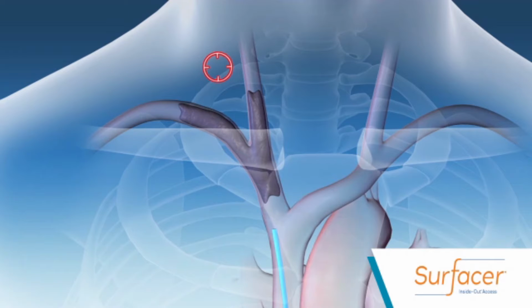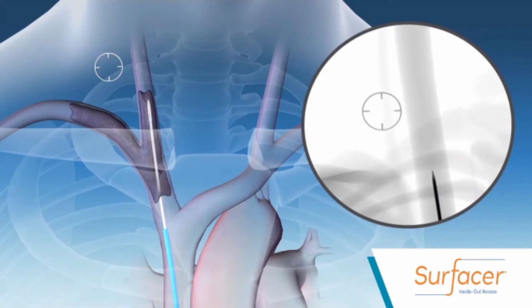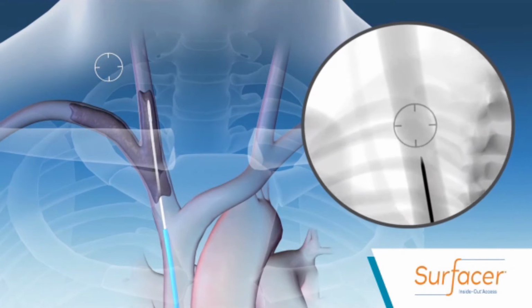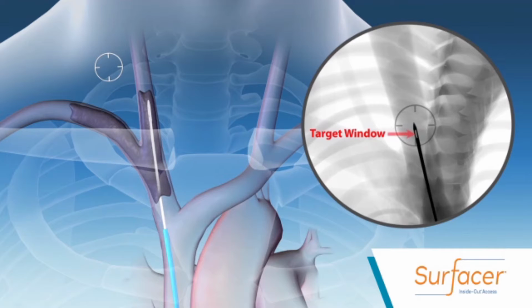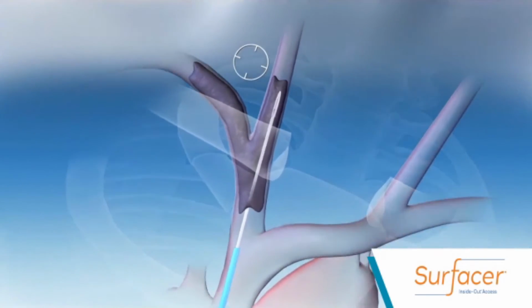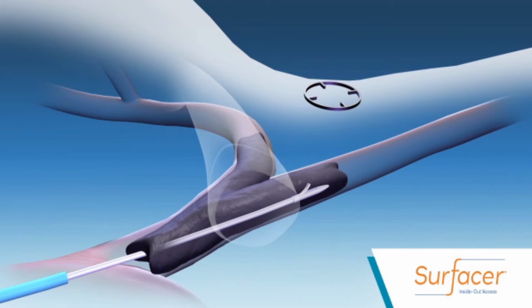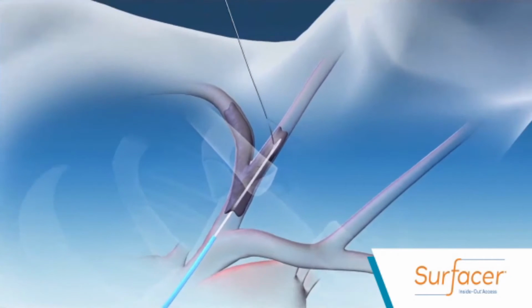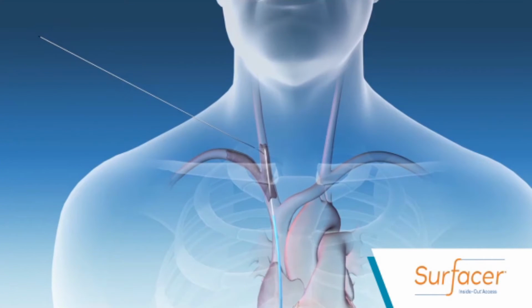After a target is placed on the exit area, the device is advanced into the obstruction. Fluoro is adjusted until the tip of the device is visible within the exit target. The device handle is rotated until the target window appears, and the needle guide is advanced out of the tip. The occlusion acts as a stabilizer as the needle wire pierces the skin at the predetermined exit point. The operator then inserts a sheath from the outside in. The Surfacer is removed, and a central venous catheter or dialysis catheter is placed using standard access procedures.